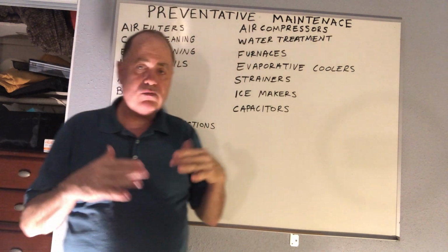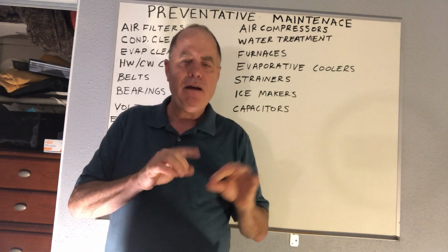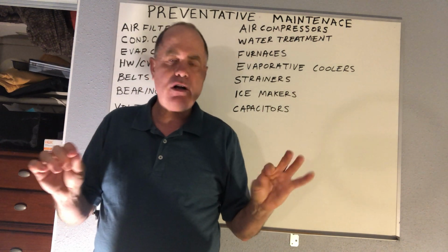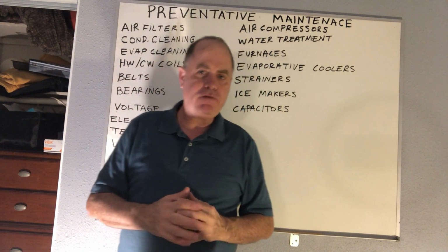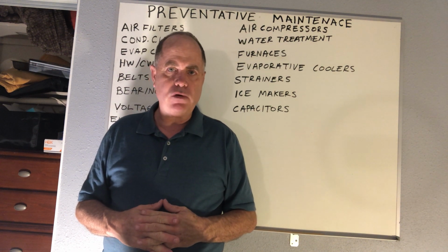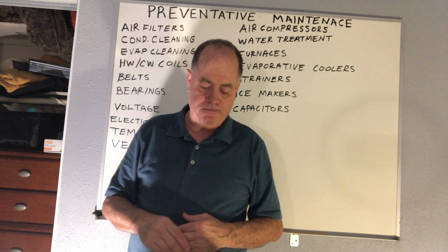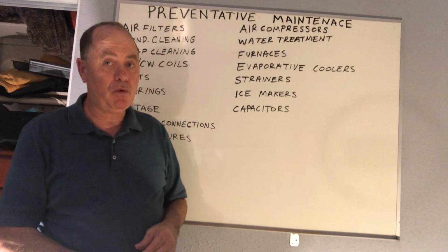So they may tell you, well, your optimum micromhos is 1458 based on the calcium in your water. If you just maintain about 1,500 micromhos with your conductivity controller in Southern California, you're going to be good, and you're going to be saving as much water as possible. Okay, I've done a lot of water treatment.